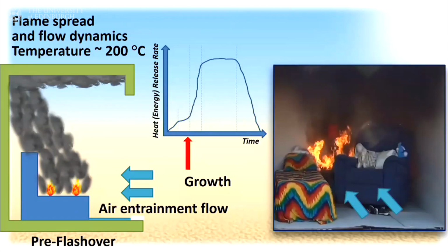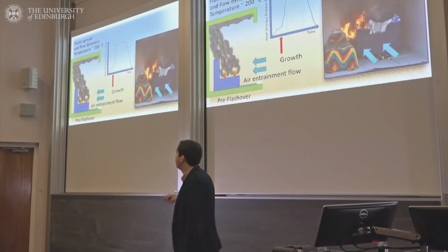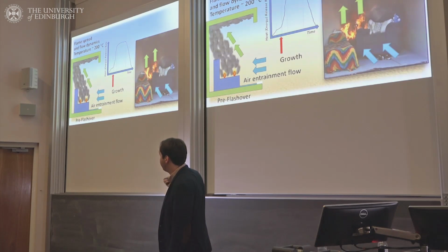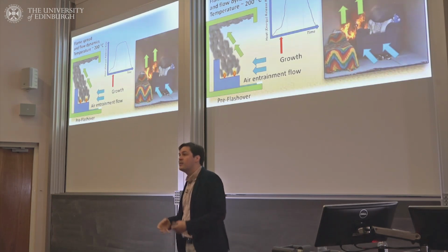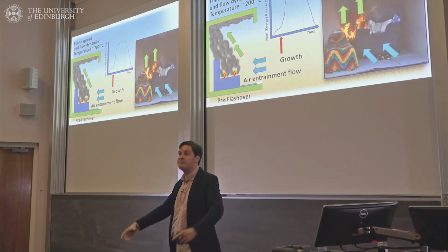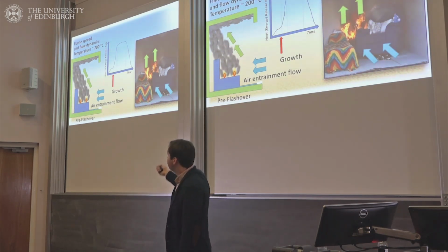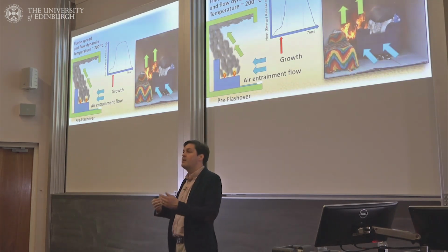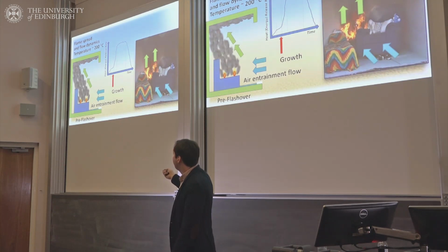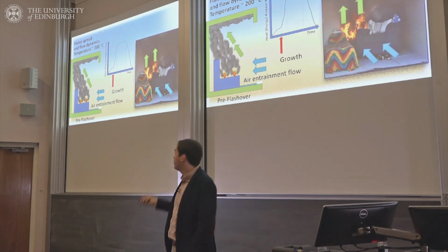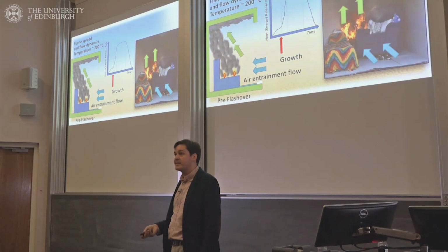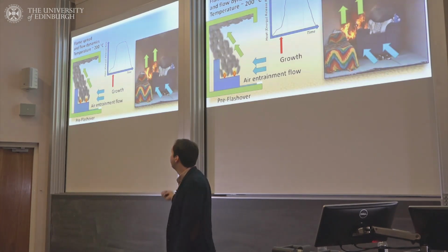So we've still got that fire, but it needs air. It needs oxygen. So we've got this air flow coming in to the room. And that is helping to drive the hot gases up, and that's why we have this slight tilt in our smoke. If it was in a nice big open space, we'd have a nice symmetrical plume going up, a nice conical shape. But when you start adding it into a compartment where you have a restricted amount of air coming in, that plume starts to be pushed towards that back wall. And in this case, that would be pushed toward that curtain. So that's going to be another fire spread mechanism.